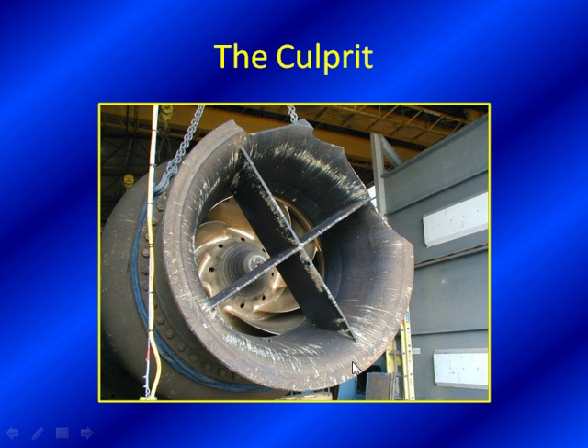And lo and behold, here's our culprit. It's not always that we get these good pictures, but we appreciate it when users send them to us. This is the inlet valve to the pump. This is a pump that's placed down into a basin - a cooling tower basin - so that it's pulling water into it. You can see that the inlet bell is broken and cracked. That crack can create turbulence and flow along the diffuser that may not be corrected, resulting in differential pressures that cause fluctuations. We're always concerned about where the broken pieces went - did they go inside the pump? Anything at this level of damage needs to be acted on quickly, and there's concern about turbulent flow through this pump.